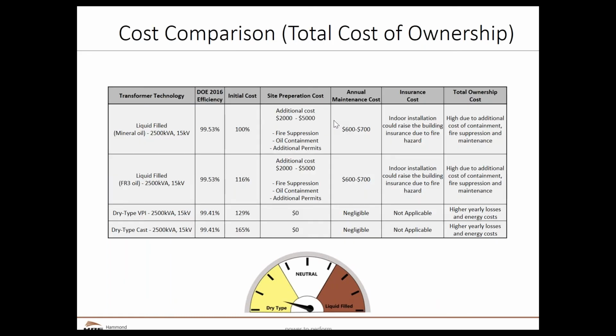Cost comparisons can be difficult. So a few things. Generally speaking, liquid filled transformers will cost less per kVA than dry type. And how that cost is attributed can be very difficult. A lot of the cost potentially has to do with what the BIL rating is, what the voltage rating is, and what type of liquid you are using. If you are going to be using especially a modern ester oil or a silicone fluid, those will cost significantly more per kVA than, let's say, less expensive mineral oil or even oils that are less benign than that.